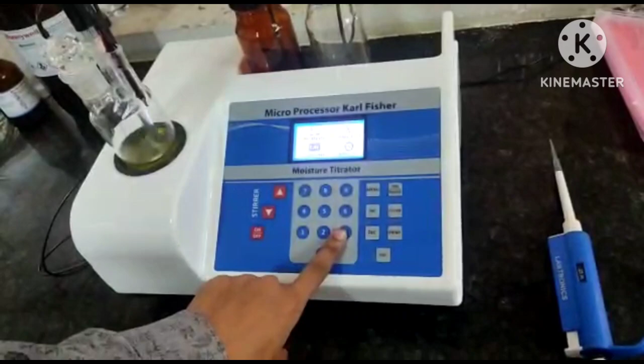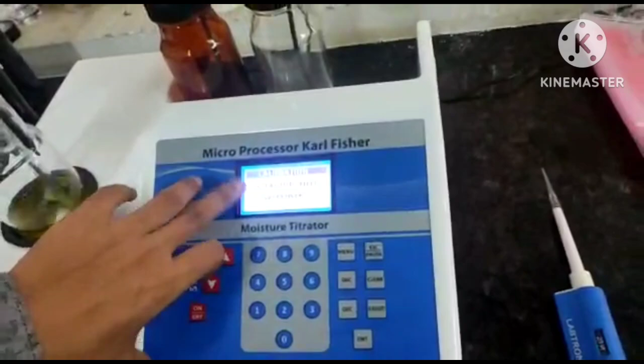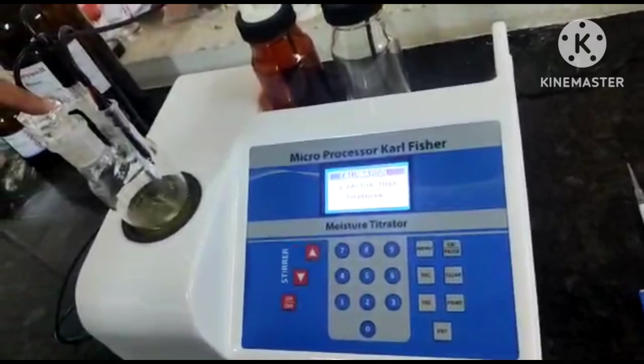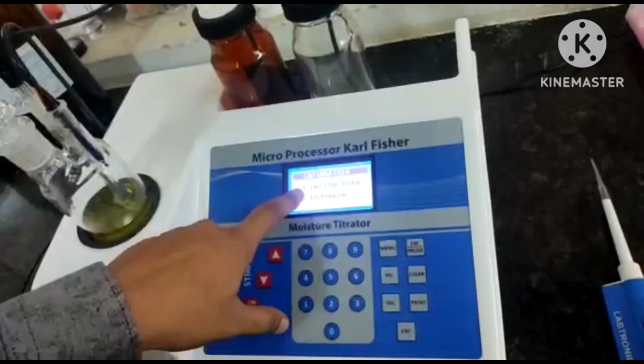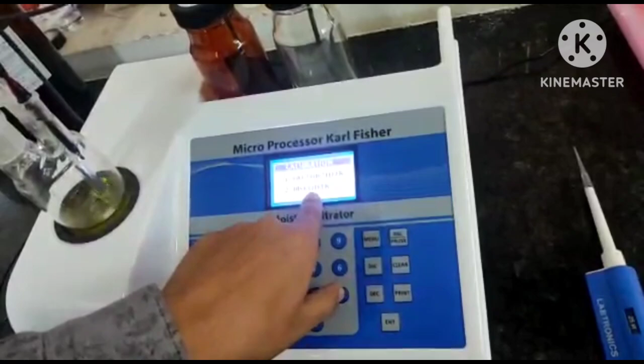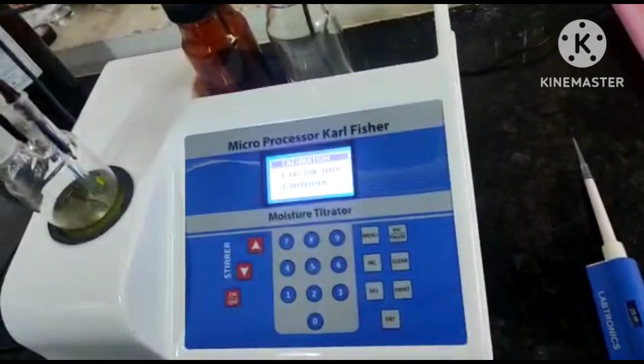For calibration, we have to go for the option number 3. So we have selected option number 3 now. As you can see, in option number 3 we have 2 options again. One is factor calibration, then second is dispenser. Dispenser is the amount of Karl Fischer agent dispensed by the motor, that we can calibrate also. And the first number is the factor calibration. So generally we do factor calibration. The second option is automatically calibrated, so you don't need to calibrate it regularly.